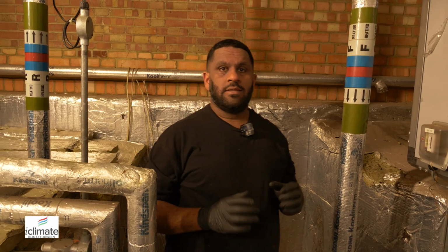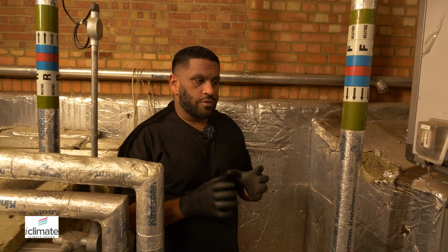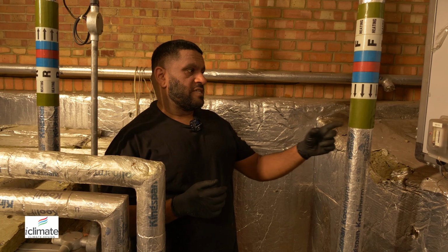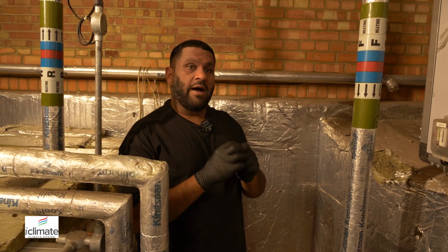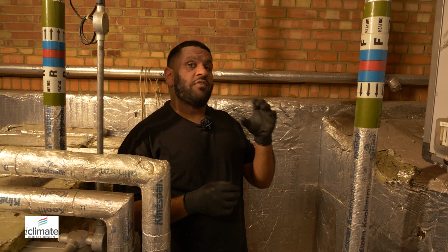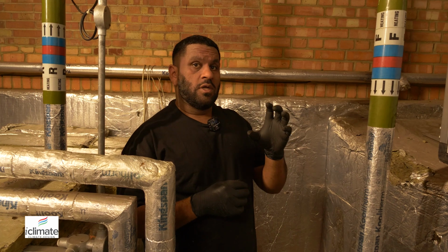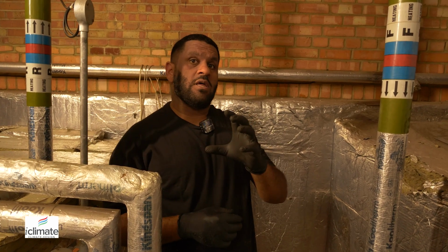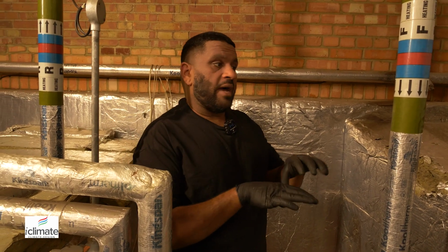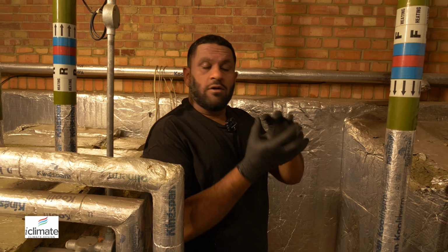To maintain this large machinery, you need to have a good understanding of mechanical, how the physical aspects of the valves actually work, the control devices of how the valves are controlled, and then the control system that controls them and how it would operate and how that has an effect and bearing on everything else integrated to it, like the cooling and heating coils.